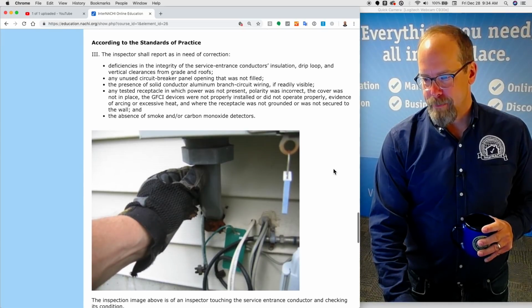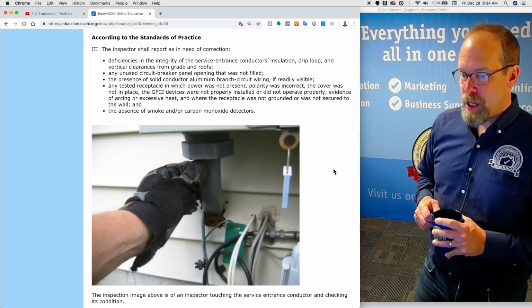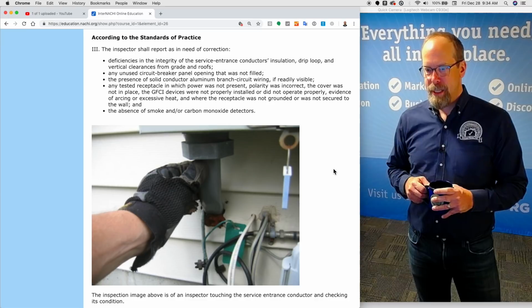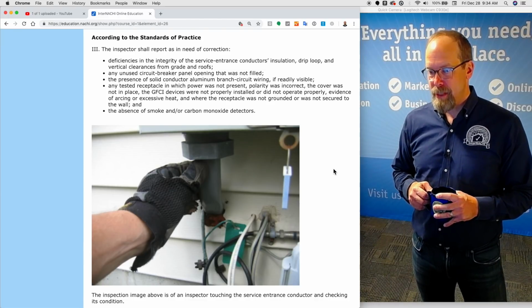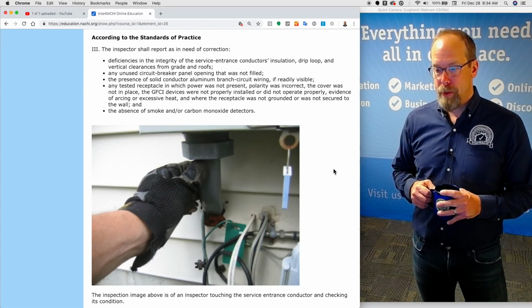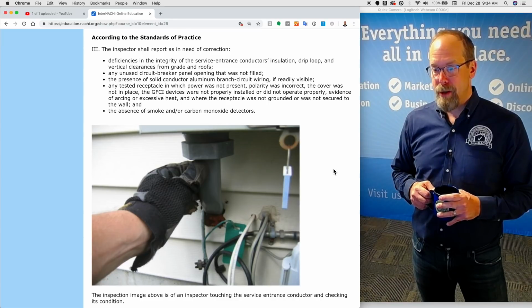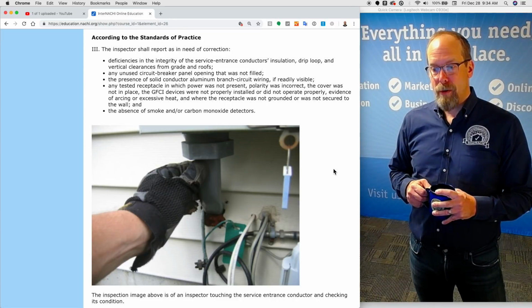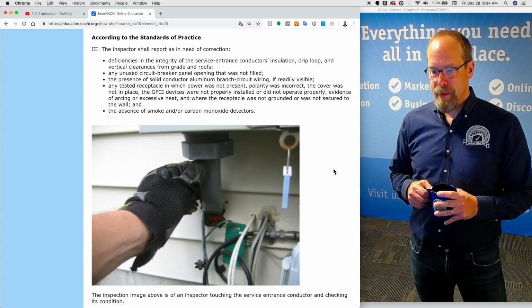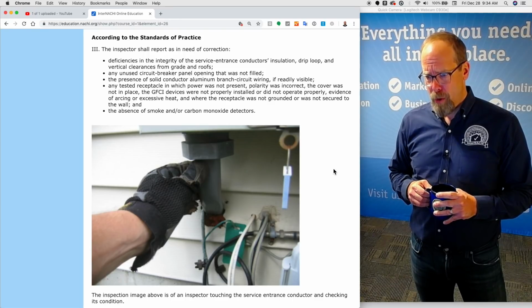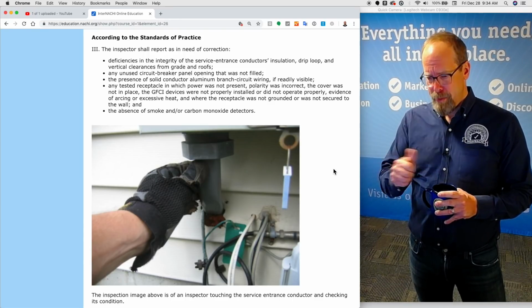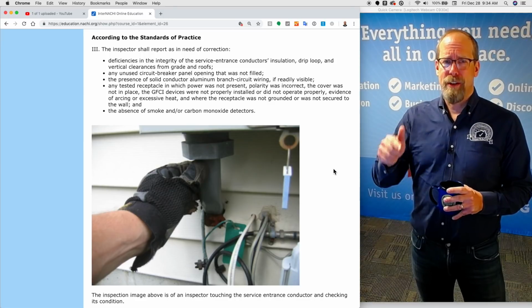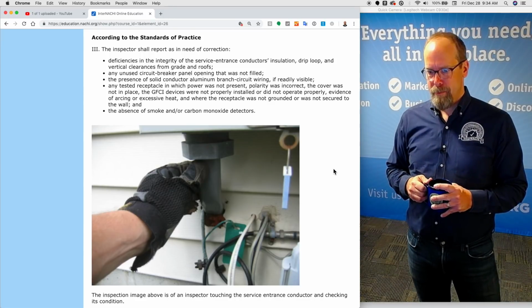According to the standards of practice, the inspector shall report as in need of correction deficiencies in the integrity of the service entrance conductors' insulation, drip loop, and vertical clearances from grade and roofs. The inspector shall report as in need of correction any unused circuit breaker panel opening that was not filled. There should be no openings there. If you stick your finger in there, you get electrocuted.